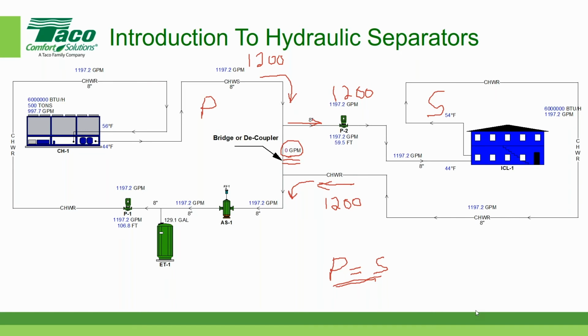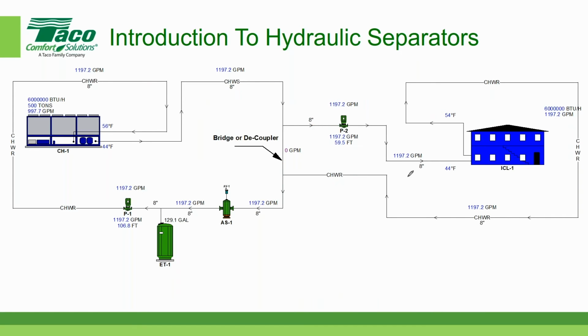Now let's talk about the third. What if my primary flow is 1,200 gallons per minute, but I'm not drawing off 100% of that flow, so I'm just going to arbitrarily make this 600 gallons per minute. I know this seems a bit elementary, but there's something we're going to cover in a minute. So we're going to draw off 600 gallons per minute. If that's the case, we're going to return 600 gallons per minute. In a moment, I'm going to ask a couple of questions from the audience. If you could just type in the answer.